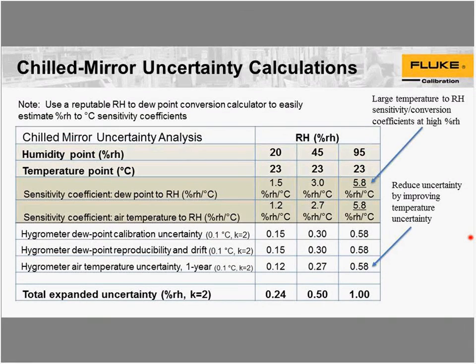Is the whole thing sent in or just the sensor? The Fluke chamber, the whole thing will be sent in for calibration. It'll be calibrated as a system.